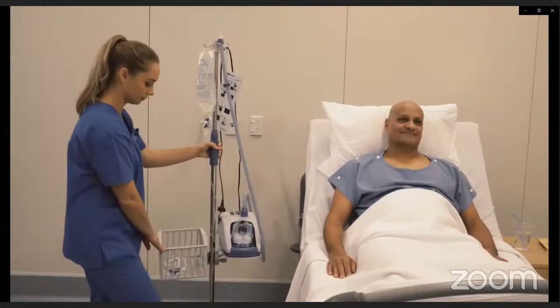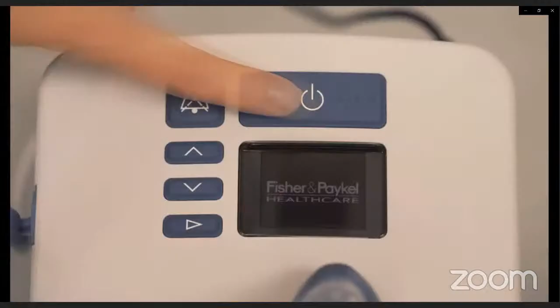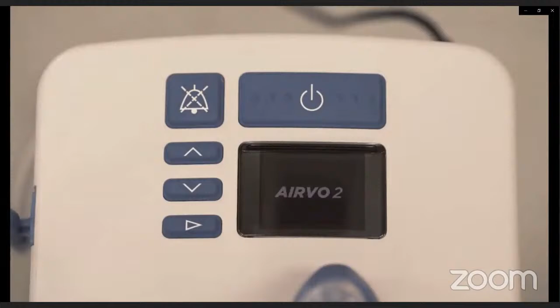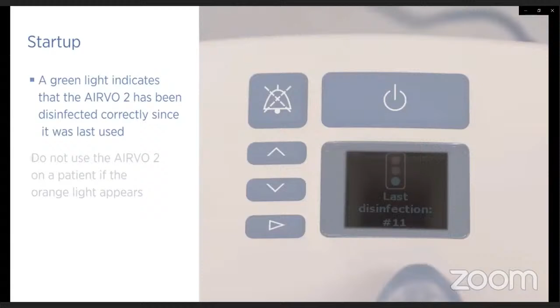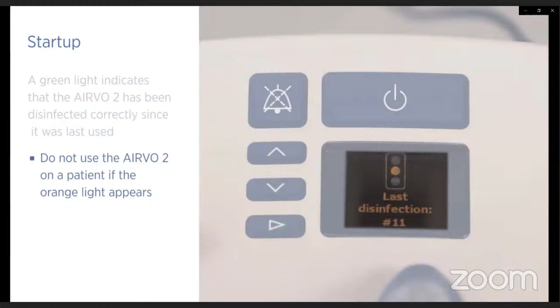With setup complete, the Airvo 2 is now ready for your patient. The Airvo 2's power cord should be well secured to the rear of the unit before plugging into the mains utility power socket. Switch on the Airvo 2 by pressing and holding the on-off button for 5 seconds. The unit will show you whether it is safe for use on a new patient. A green light indicates that the Airvo 2 has been disinfected correctly since it was last used. However, do not use the Airvo 2 on a patient if the orange light appears. You must dispose of the consumables and reprocess this Airvo 2 before it can be used.